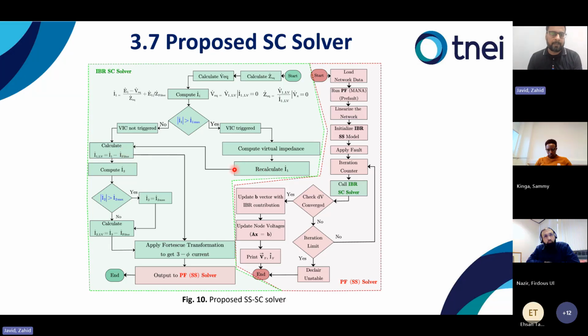And after calculating that, we will compute I2, and then we check again: if I2 is greater than I2 max, we set that value equal to I2 max, so it will not exceed that limit. And then after that, we will calculate the reactive current and negative sequence current on the LV side of the transformer as well, minus the filter current, so it will give that LV side current.